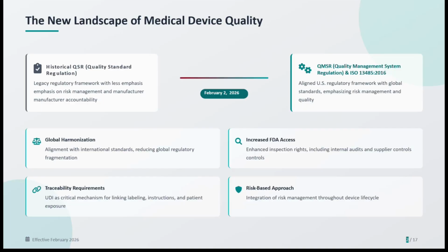On February 2nd, 2026, current quality standards transition from the historical Quality System Regulation, or QSR, into the new Quality Management System Regulation, or QMSR, that is aligned with ISO 13485. The legacy QSR was a US-centric framework with limited emphasis on structured risk management and lifecycle accountability. With the new QMSR aligned to ISO 13485, again, a global standard, the expectations for documentation and labeling are significantly elevated. Documentation is now clearly treated as a regulated, controlled output.